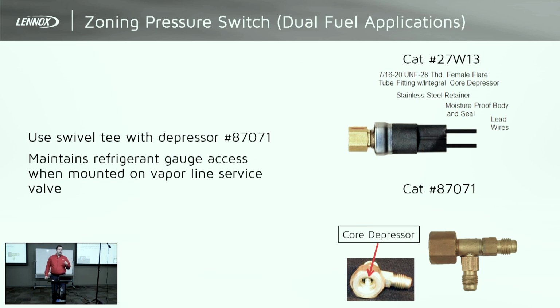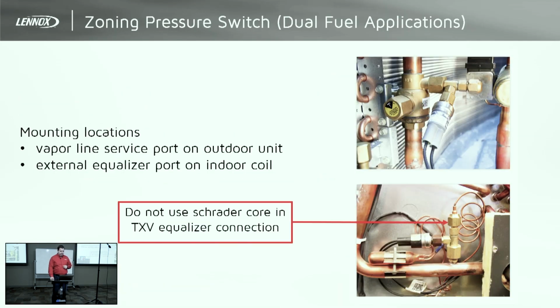Now, what's important to understand about this thing, because this little guy will get you in trouble, is that it can be installed in a couple different ways. It can be installed out here at the outdoor unit. You can piggyback it onto the vapor line service valve. Now you have to have 2 conductors going outside specifically to tie it back to your zone board. Or you can piggyback it here onto the equalizer line port. Where a lot of guys get into trouble with these is they don't take the Schrader core out of this little brass fitting that you add onto it.